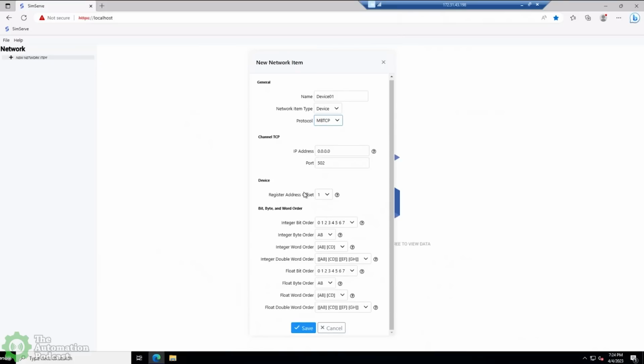Next, register address offset can be either 0 or 1. The Modbus standard actually requires devices to use 1, but a lot of manufacturers have different thought processes. Sometimes devices were developed before the standard was locked in, so in some cases you'll have to switch that to 0.